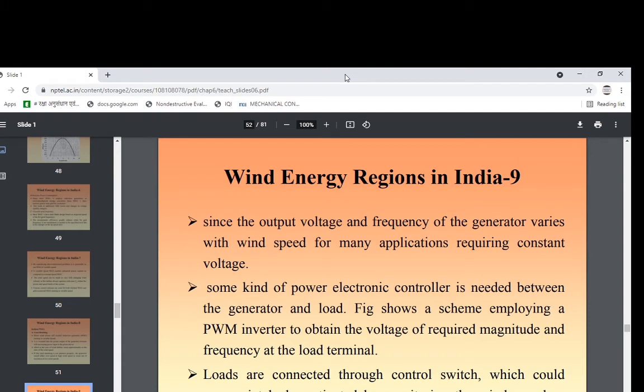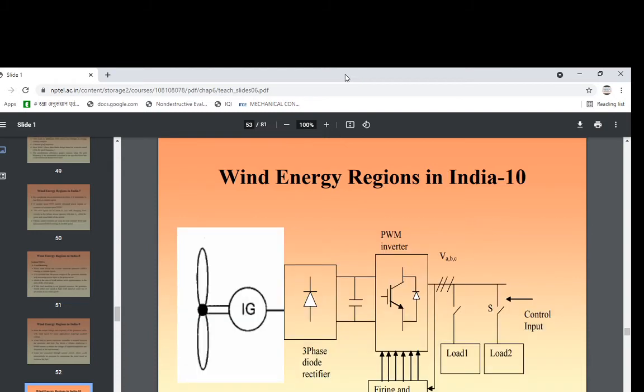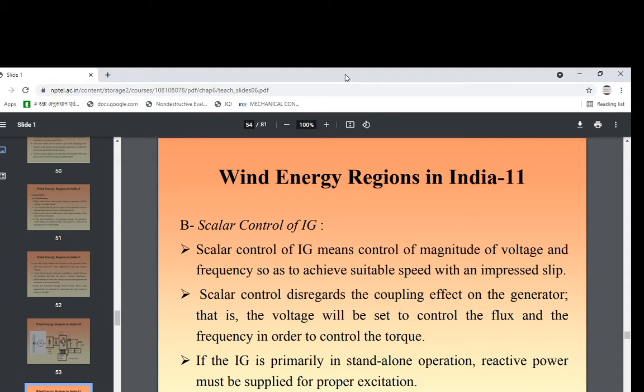This shows a scheme employing a PWM inverter to obtain the voltage of required magnitude and frequency at the load terminal. The loads are connected through a control switch which could be activated by monitoring the wind speed, as shown in the figure. This is the figure: wind energy regions in India, with the three-phase diode rectifier, PWM inverter, firing and control circuit unit, load 1 and load 2.